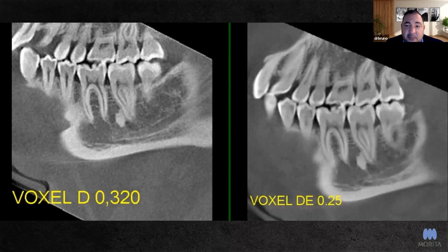particularly for those who work with larger fields of view, the X800, we can actually change the resolution of your reconstruction. So the native reconstruction right now for the larger field of view of the X800 is 0.32 millimeters, right? So 320 microns. Right now, we have the capability to change the voxel size from 0.32 to 0.25. This is something that I was discussing with Mr. Sliman before this meeting. So you would have to contact your engineer, your Morita dealer, and they will log in remotely and perhaps maximize that image quality for you on your scans.